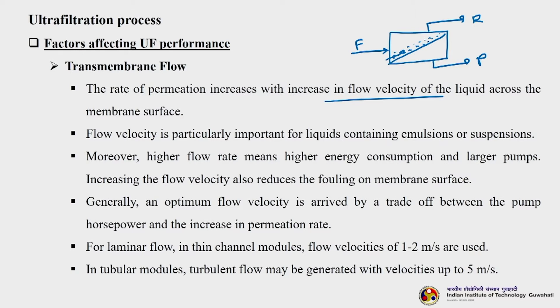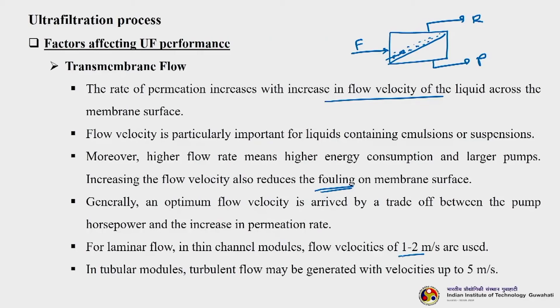Higher flow rate means higher energy consumption and larger pumps — it is not always a win-win situation. Increasing the flow velocity also reduces fouling on the membrane surface. An optimum flow velocity is arrived at by a trade-off between the pump horsepower and the increase in permeation rate. You simply cannot keep increasing cross-flow velocity as you wish. For laminar flow in thin channel modules, flow velocities of almost 1 to 2 meters per second are used, and in tubular modules where turbulent flow comes into picture, we can go up to 5 meters per second.